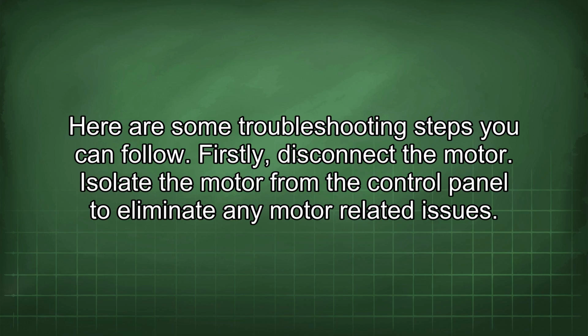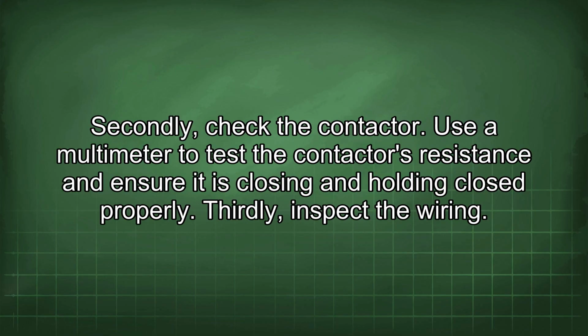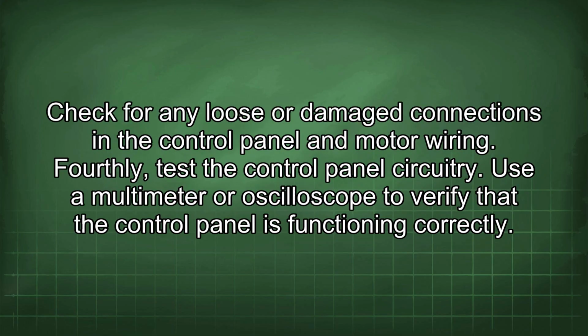Here are some troubleshooting steps you can follow. Firstly, disconnect the motor. Isolate the motor from the control panel to eliminate any motor-related issues. Secondly, check the contactor. Use a multimeter to test the contactor's resistance and ensure it is closing and holding closed properly. Thirdly, inspect the wiring. Check for any loose or damaged connections in the control panel and motor wiring.